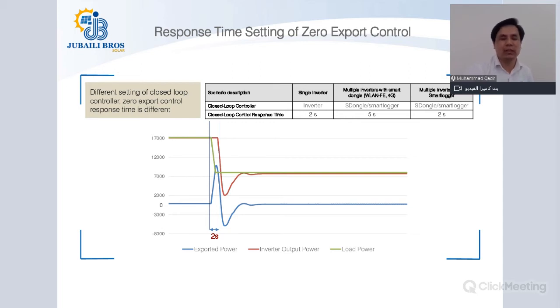So sometimes your consultants or requirement from the customer side would be to make sure that this response time is less than 10 seconds or 5 seconds or 2 seconds. So you make sure that you are using the right type of control mechanism in order to meet the criteria of your consultant, in order to control the output power of your PV plant.